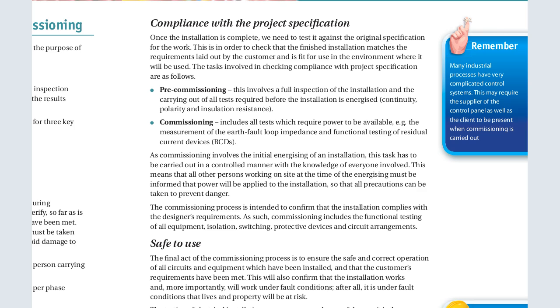That is, it is also called the continuity, polarity, and insulation resistance test. We are going to look at this type of test and how it takes place. Another one is commissioning, which includes all tests which require power to be available, e.g., the measurement of the earth fault impedance, the earth loop impedance.